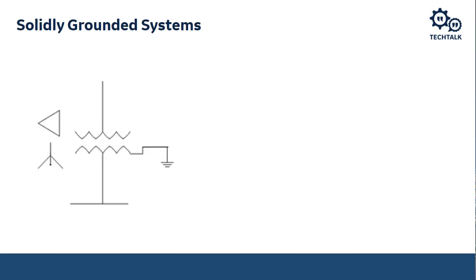So what are the methods or scenarios by which we can introduce a ground in a system? One is to solidly ground the system. Especially if you have a transformer with a Y winding, we can solidly ground that Y winding. However, once we do that, we introduce high ground fault levels because once we get a phase-to-ground fault, there's no impedance or hindrance for the ground fault current to flow. So now we have high levels of ground fault current, which we can easily detect because overcurrent relays will easily detect those high fault currents.